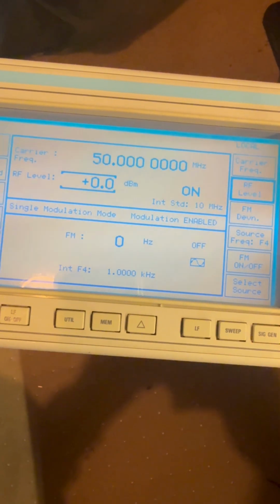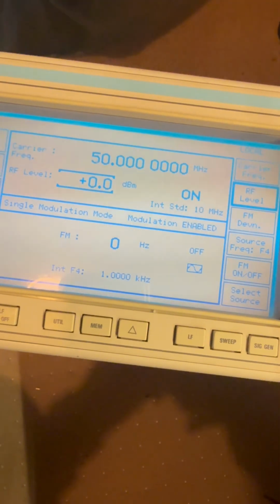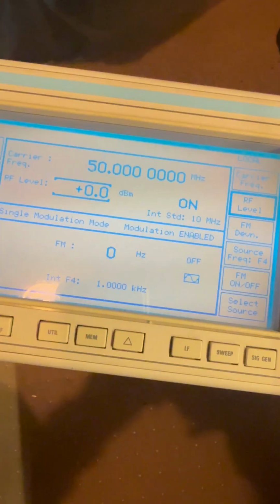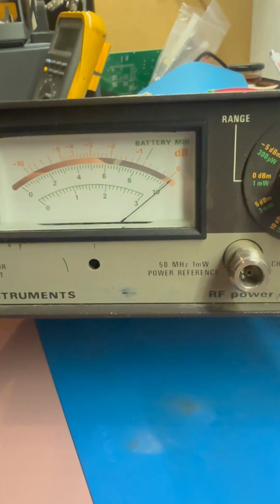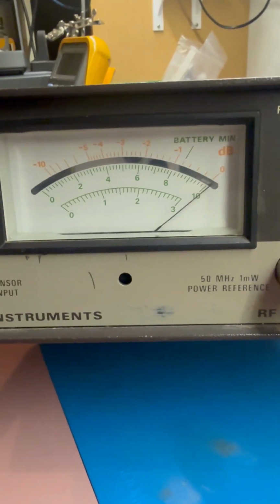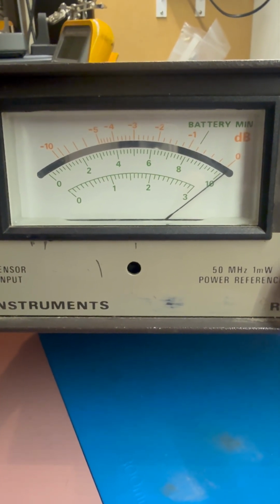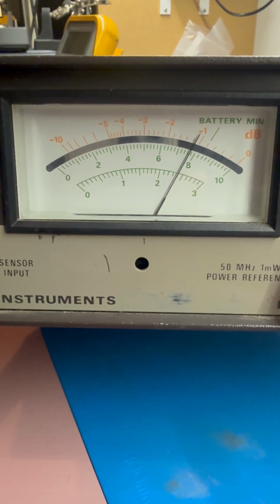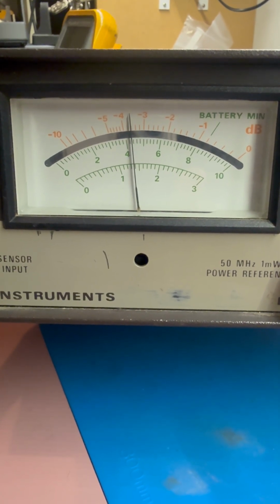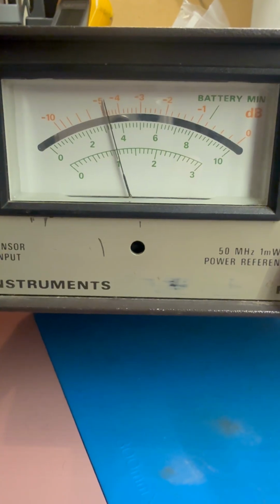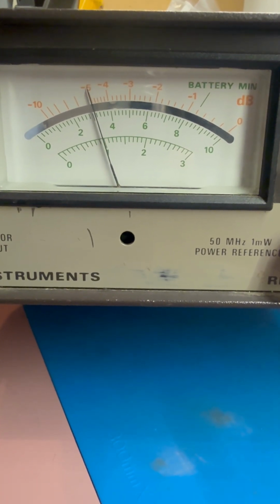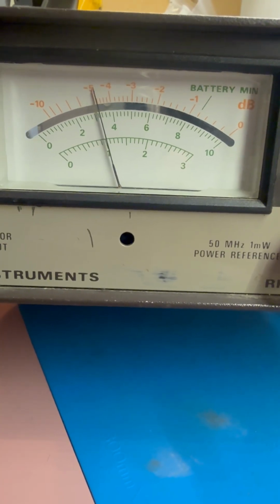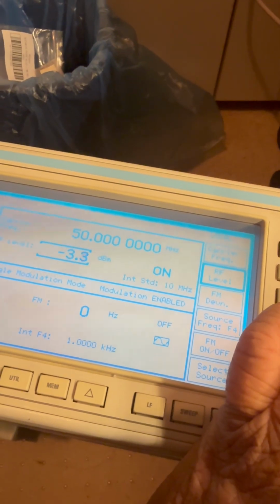We're using the Marconi 2031 frequency generator set to 50 megahertz and putting out 0 dBm with no modulation. The power sensor is connected to the output, and we go back to the meter here and we can see the meter being up at 0 dBm, and now I'm winding the output back to minus 5 dBm. It's about minus 5 dBm. Have a look. There we go, that's sitting at about minus 5 dBm. Let's just adjust it to a different number and go to minus 3 dBm.